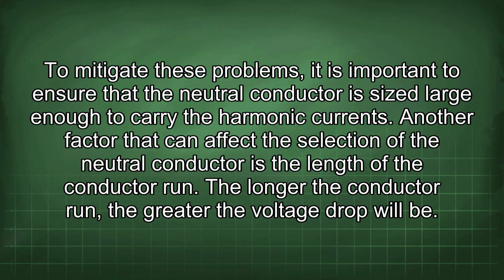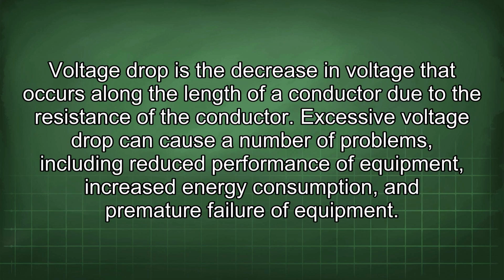carry the harmonic currents. Another factor that can affect the selection of the neutral conductor is the length of the conductor run. The longer the conductor run, the greater the voltage drop will be. Voltage drop is the decrease in voltage that occurs along the length of a conductor due to the resistance of the conductor.